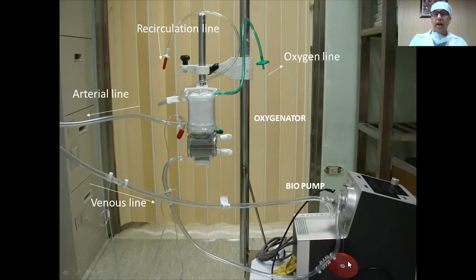And you can see the console. Through this console, we can adjust the oxygenator and the run of the ECMO. So ECMO is an integration of machine as well as the patient. And here, the person behind the ECMO machine is probably more important than the machine, because he has to monitor the patient parameters, monitor the ECMO parameters, and monitor the integration of these two so that the maximum benefit of ECMO can be achieved in any patient.